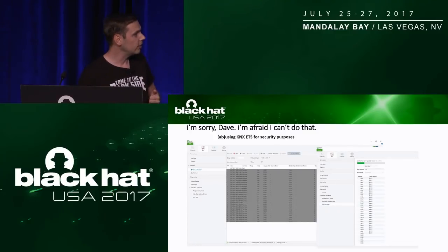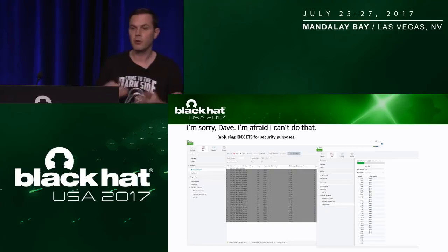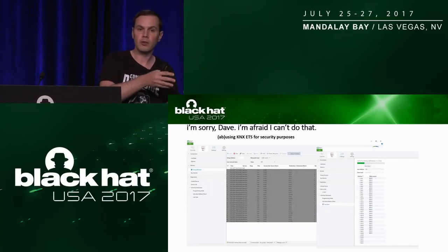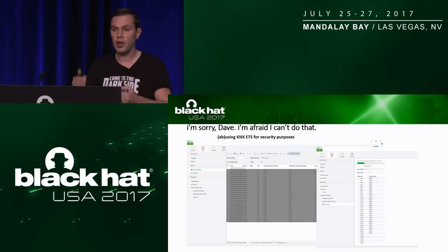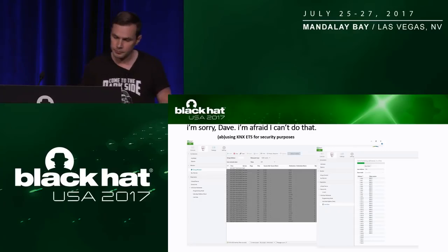And on the left side, you have the source addresses, and on the right side, you do have the destination addresses. So this is very interesting to learn who is talking to whom. Which addresses are being used by the sensors and which addresses are used by the core controller. Most probably the core controller will show up on the destination side most often.